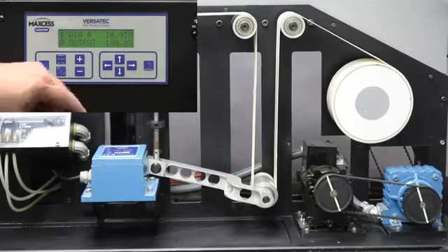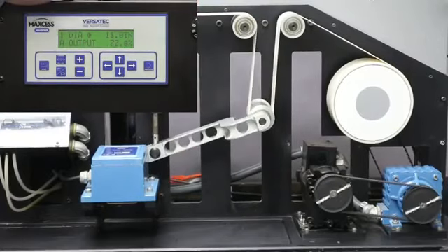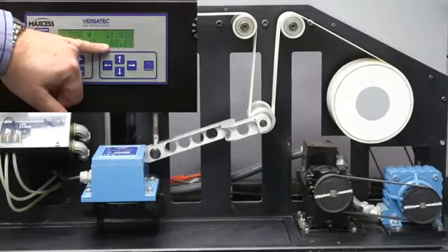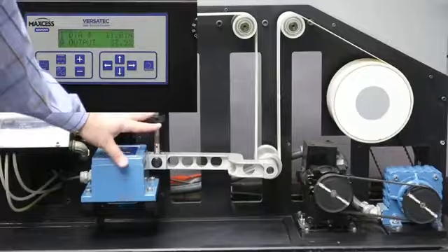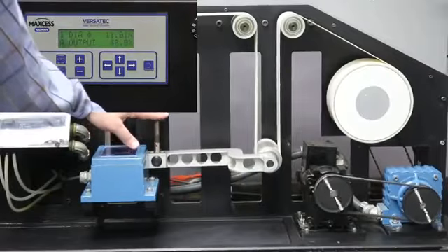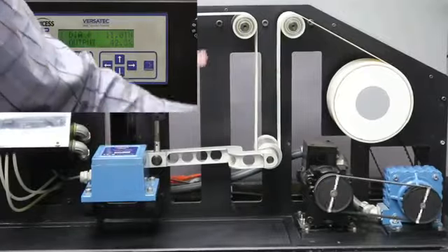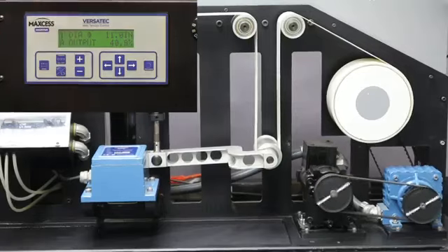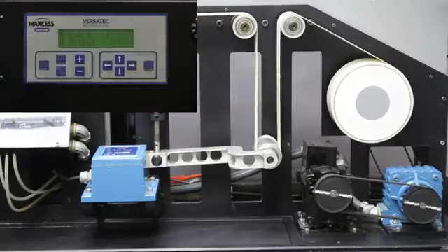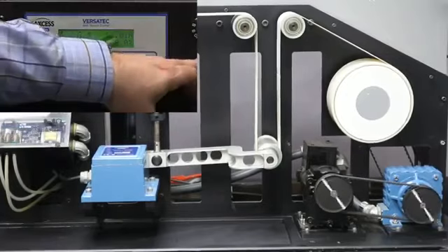And watch what the arm does when I turn it back on. Now my arm has gone up, hit the top stop, until it can integrate back down to that point. And as soon as I hit that stop, I have lost my tension control. Remember, it's only a tension control if it's not hitting the top stop or the bottom stop. So it's very important to connect what we call a run-stop connection on these. So rather than using the speed of the machine to stop the web, you should use a run-stop connection.